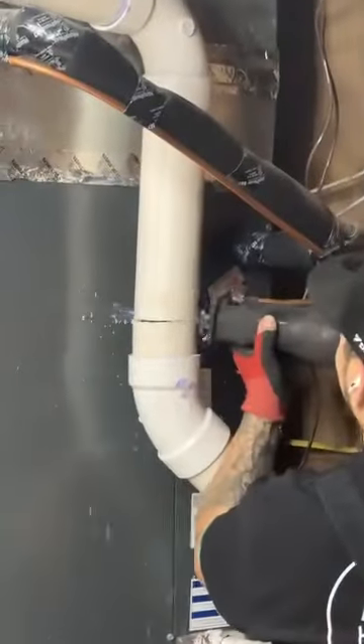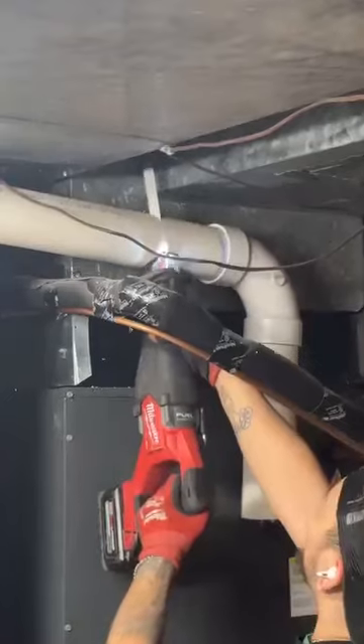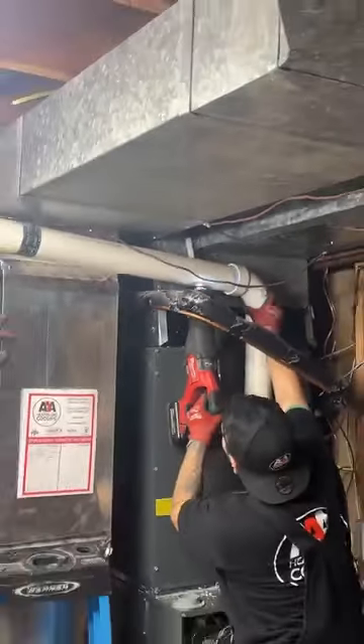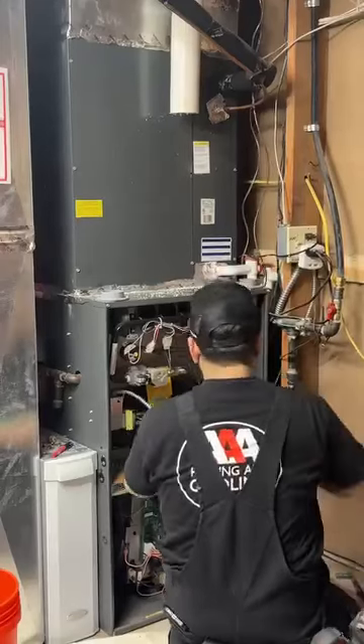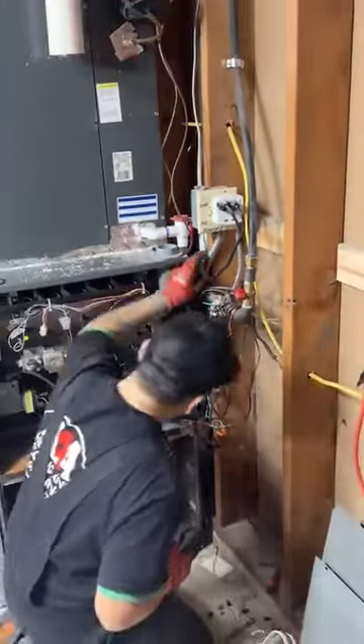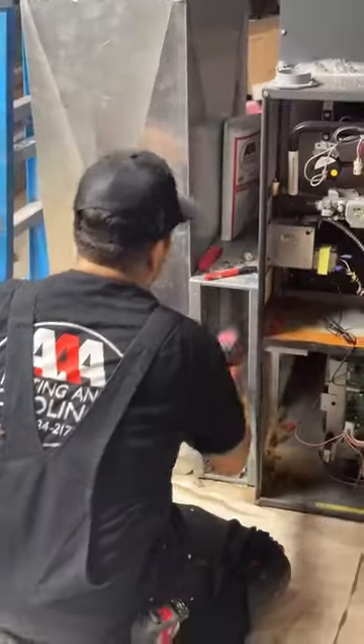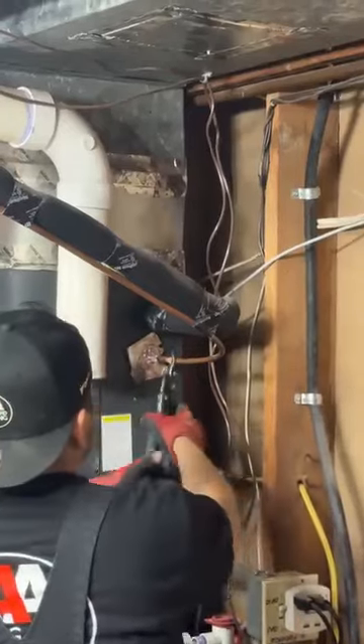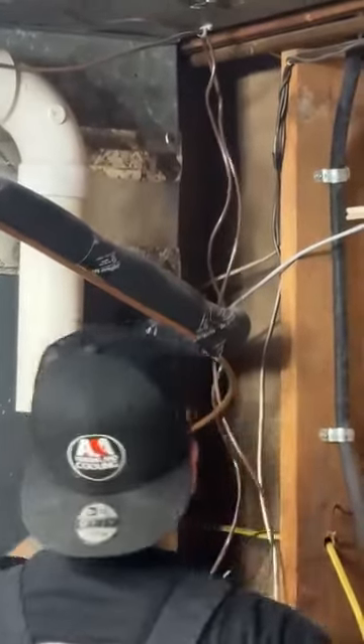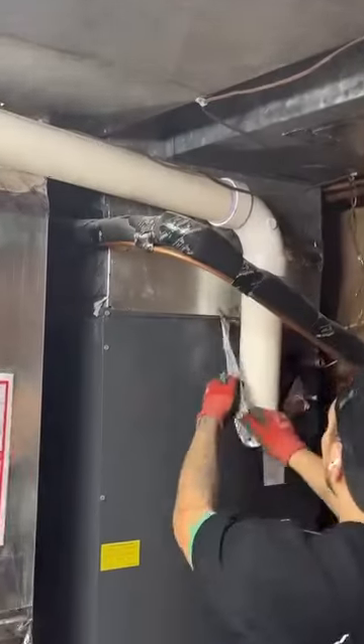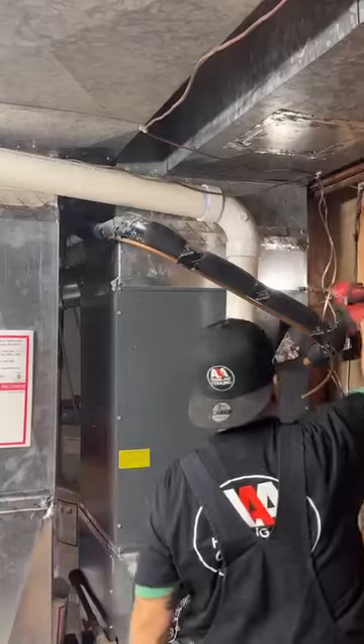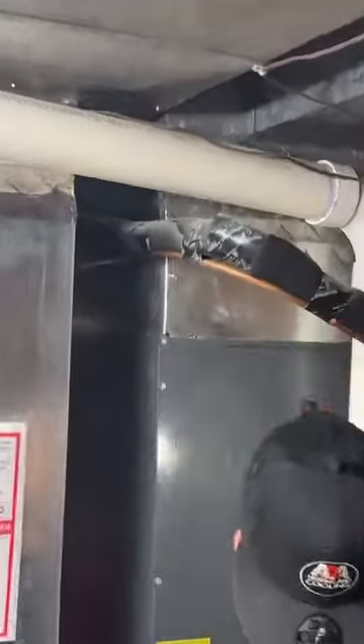Since this is a 90% furnace, we next remove the old exhaust PVC pipe. After the exhaust piping is removed, we continue to disconnect all electrical wiring housed in the old unit as well as the condensate pump, and begin to detach the old furnace from the filter cabinet and supply return. Once the outdoor unit has been drained, we cut the old refrigerant line. Next, we remove the old air leak prevention tape and begin disconnecting the supply plenum from the old unit.